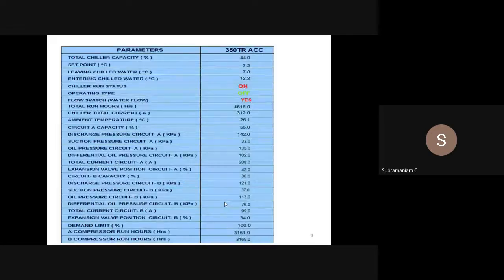Correct? Then similarly, we have an air-cooled chiller. What are all the values? Set point is 7.2, leaving is 7.8. So the chiller technician will come and see all these values and see whether my expansion valve position is correct, my compressor capacity is okay, all that kind of information. There are a host of 25-30 parameters which we have integrated through BACnet. Through BACnet, we are getting all the parameters by using one pair of twisted shielded wire of 2 core 1.5 square mm.